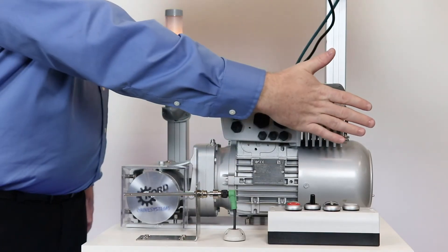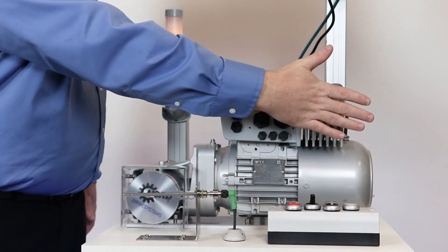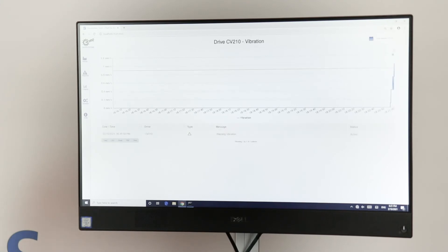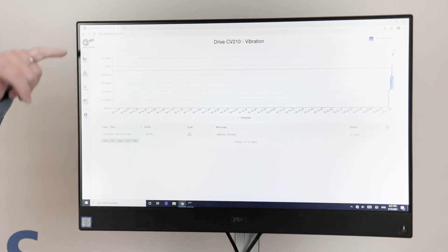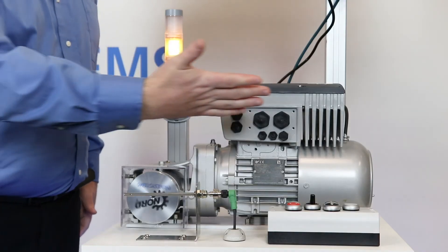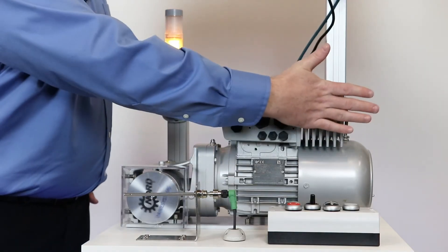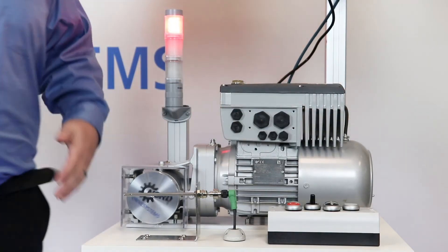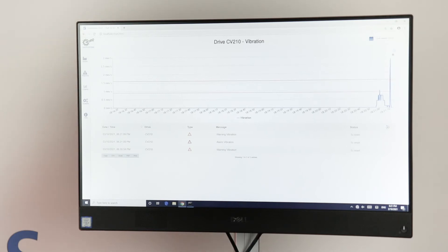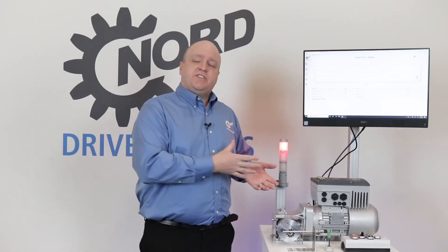If I go ahead and give it some slight bumps, we can see that I've exceeded the warning threshold, and if things continue to deteriorate — hitting a little bit harder — now we've reached a warning state. In this case the VFD is going to continue to run.